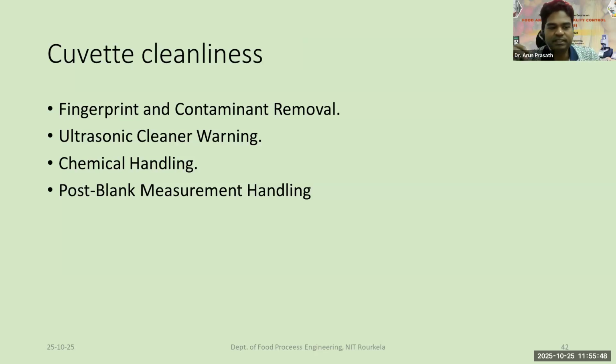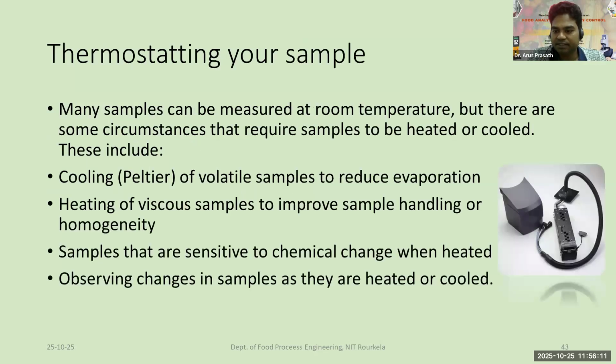Presence of impurities and fingerprints on the cuvette has to be removed with ultrasonic cleaners, and chemical handling should be avoided. Even a small scratch on the cuvette can cause changes in the results. Post-blank measurement handling is also very important to compare the changes. And then thermostating the sample.